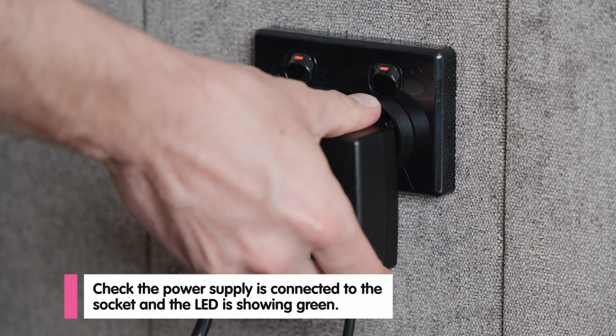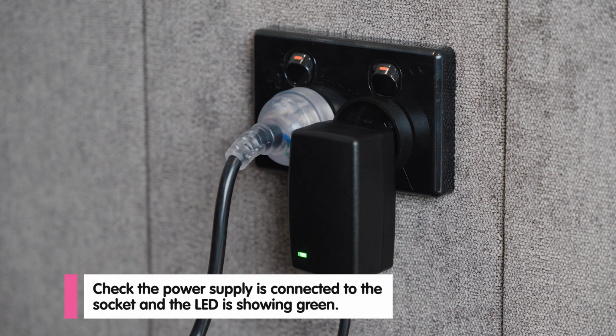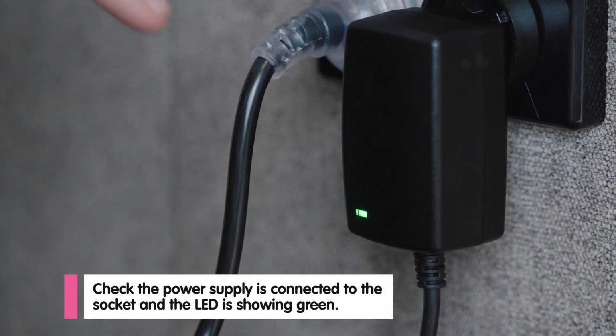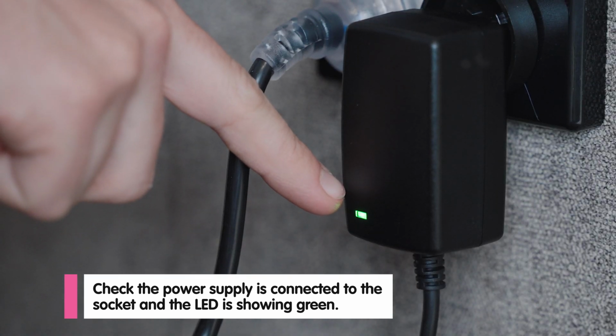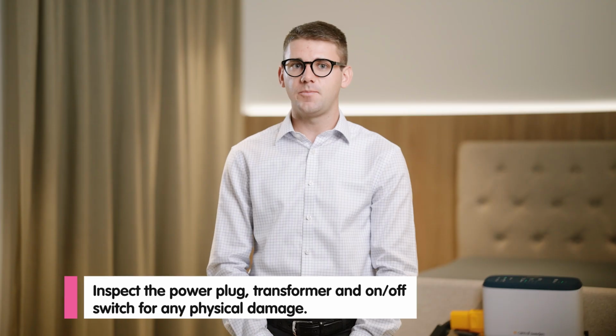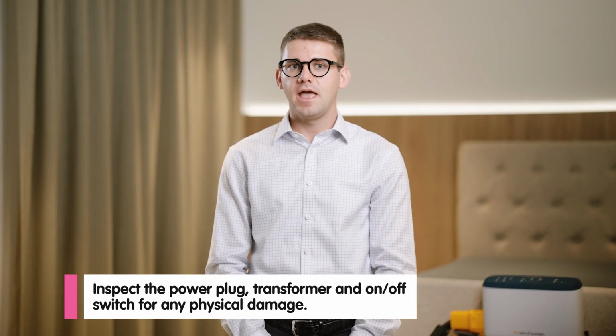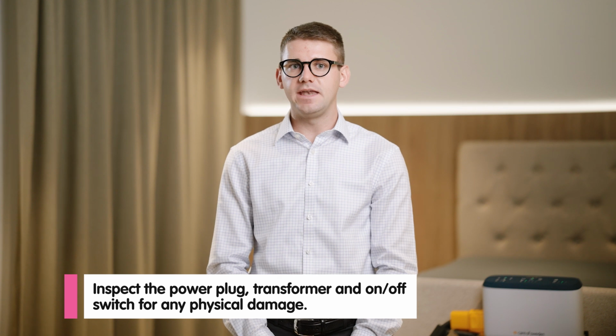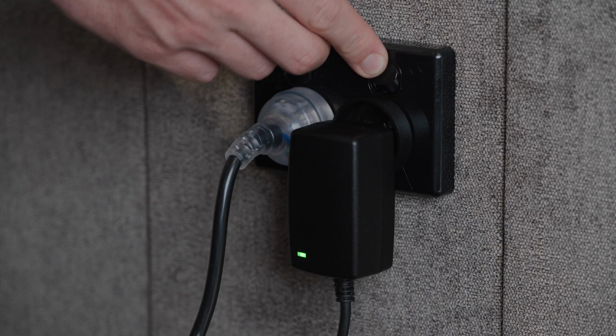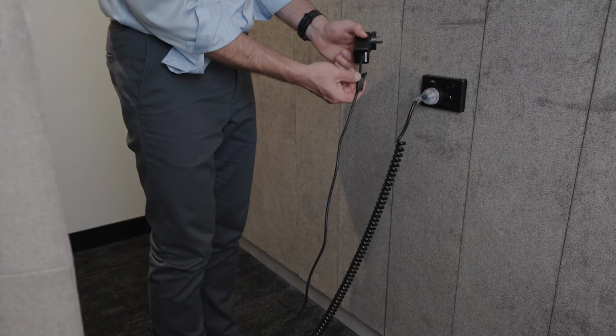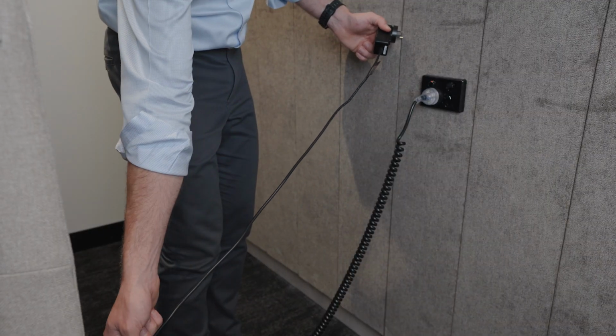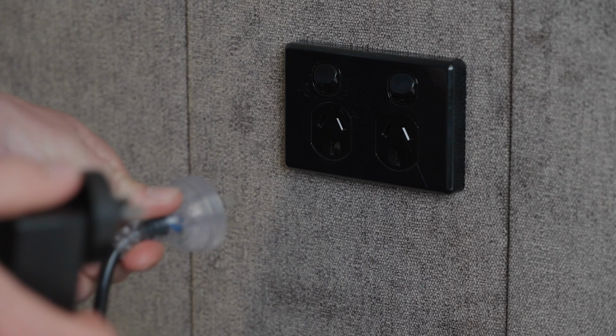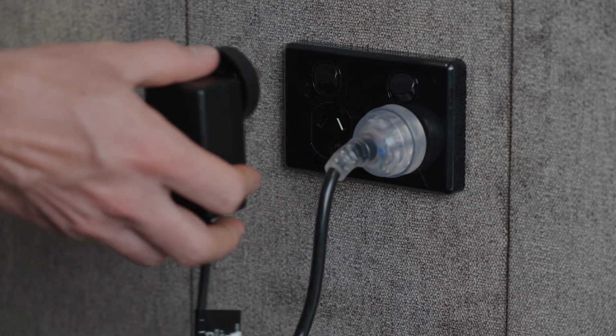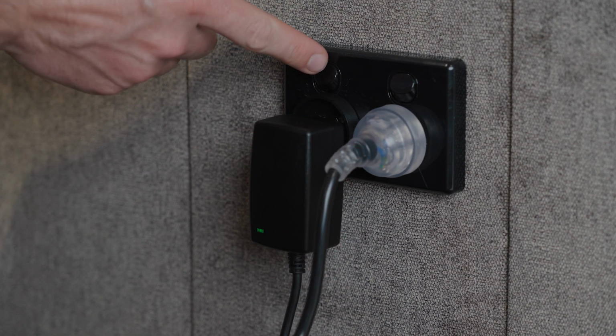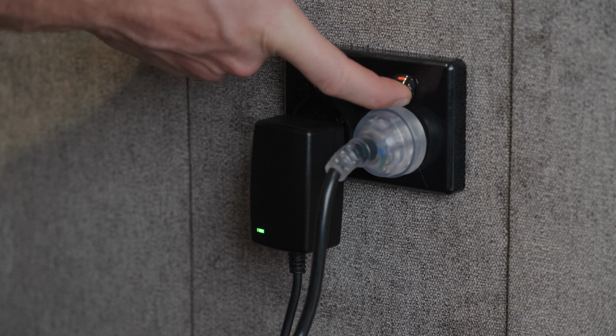If the control unit doesn't start, check that the power supply has been connected to the electrical socket. Check that the LED on the power supply is showing green. Inspect the power plug, transformer and on-off switch for any physical damage. Ensuring the cable is unplugged, carefully run your hand along the cable to check for any physical damage. To test the electrical socket, plug another appliance into the socket to see if it is operational.